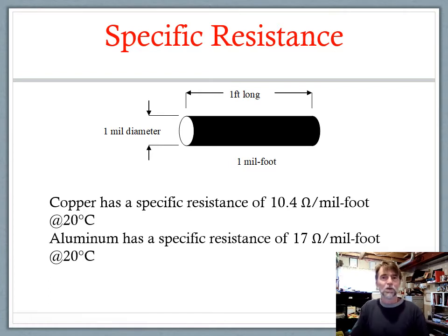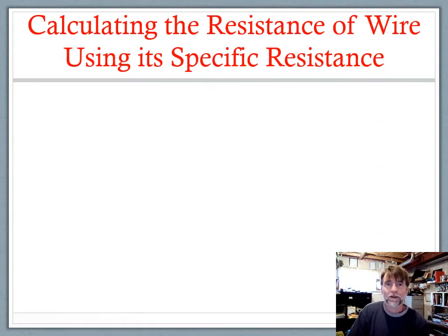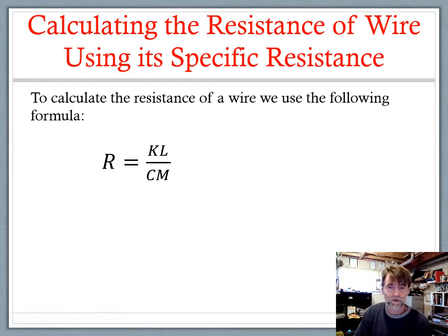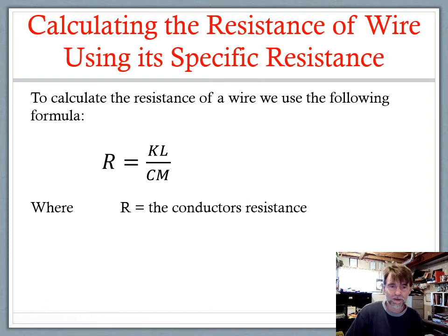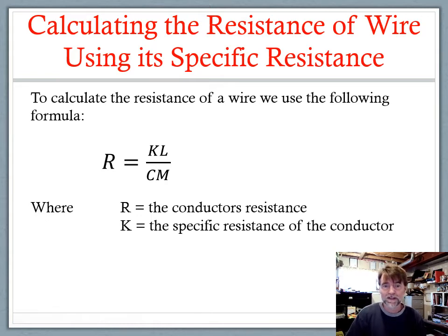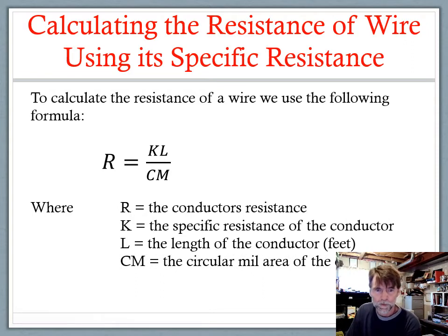Now we can actually calculate the resistance of any given conductor. In order to do that we need an equation. The formula is R equals KL over CM. R is the resistance of the conductor — that's what we're trying to calculate. K is the specific resistance of the conductor: 10.4 for copper or 17 ohms for aluminum. L is the length of the conductor in feet — it's all imperial, no metric. CM is the circular mil area.